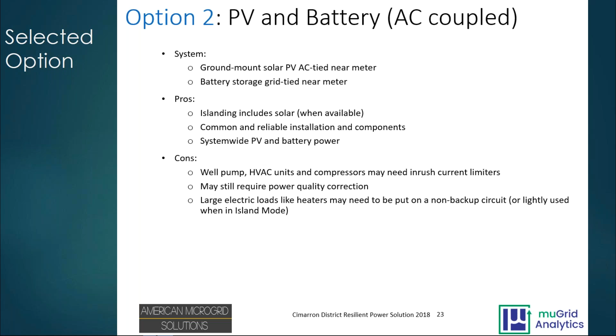AMS created a menu of options, and we selected Resilient Power 2 as our target, costing about $71,000, priced from our state pricing agreement. This included a 9.7 kW array, though we ended up sizing it on site to about 10.3 kW, plus battery sizing and generator sizing. The existing generator is a 20 kW propane unit with a few more years of life, so we kept it, giving us resilience with the generator of at least 72 hours.